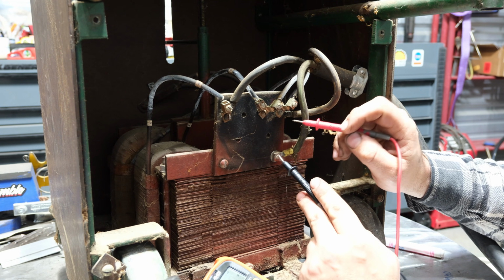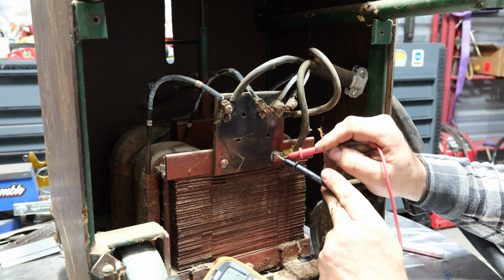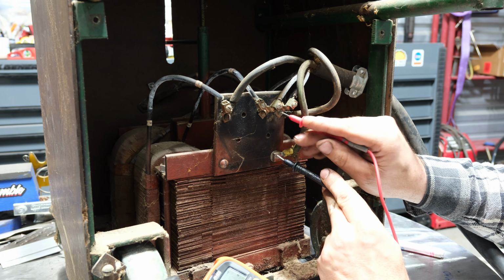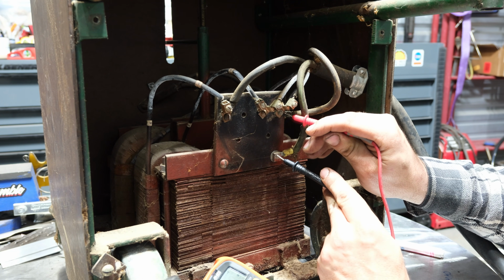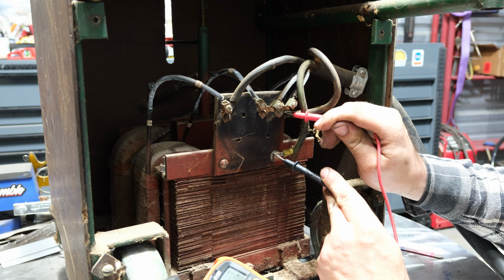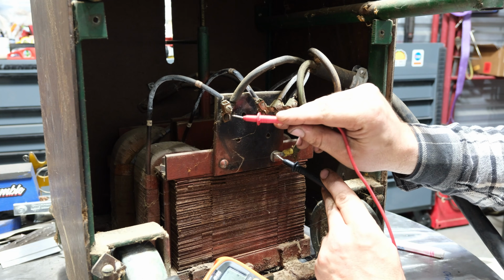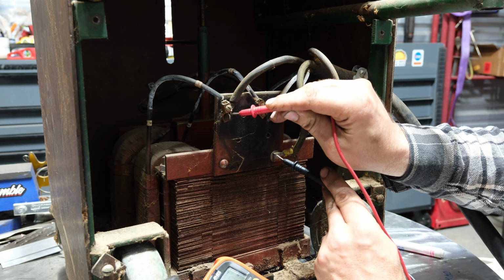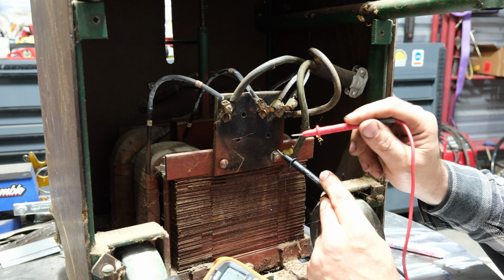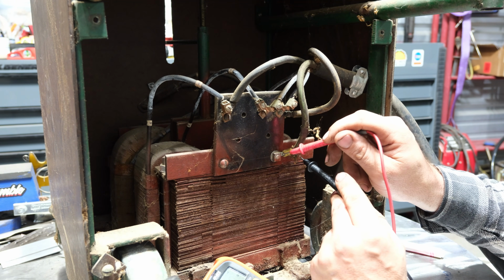we now want to confirm from the ground lug to the hot wire that we do not have continuity, and we do not. I do not hear it or see any reading. That's one wire of the 240 volt. Here is the second wire. So both hot wires coming into this transformer are not shorted to ground.